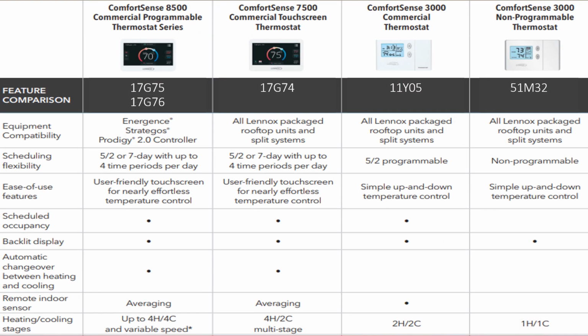So the whole lineup on the thermostats, the ComfortSense 8500, if you've got any unit with a Prodigy board, this is a no-brainer. You want to use this unit, you can make it do almost anything you want to do. The ComfortSense 7500, you can use this on all package units and commercial split systems, period, including the Energence. The ComfortSense 3000, you can use it on all package units. Just keep in mind there are options like the hot gas reheat and things like that that this probably won't control.